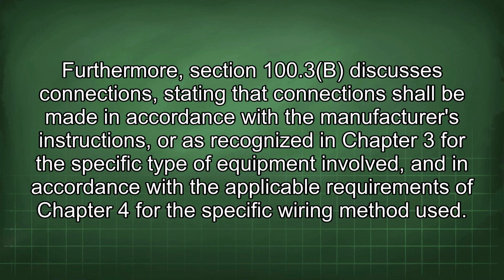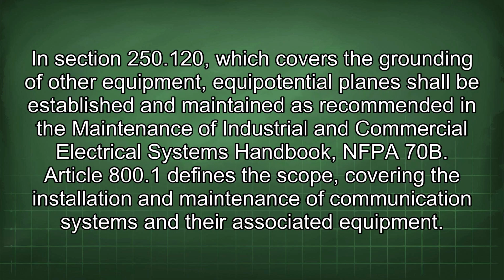Furthermore, Section 100.3b discusses connections, stating that connections shall be made in accordance with the manufacturer's instructions, or as recognized in Chapter 3 for the specific type of equipment involved, and in accordance with the applicable requirements of Chapter 4 for the specific wiring method used. In Section 250.120, which covers the grounding of other equipment, equipotential planes shall be established and maintained as recommended in the Maintenance of Industrial and Commercial Electrical Systems Handbook, NFPA 70B.